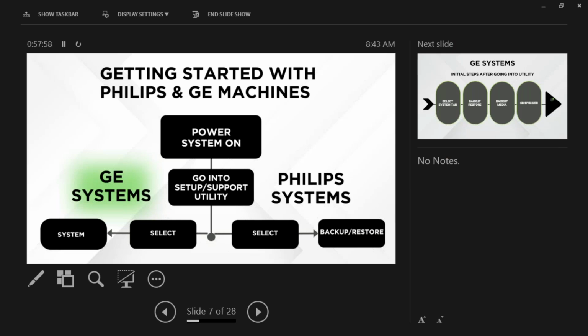Okay, so we covered depth of penetration. Again, this particular one was 15 centimeters. If you see it going 14, 12, whatever, then you know the transducer is probably having an issue. We should get it looked at. And if you have any questions, go through another curved 5.1 on there, take a look and see what the depth of penetration is on that particular one. So the next test is functional resolution test. All right. In this one, we'll use a Phantom and image the anechoic structures on the Phantom.